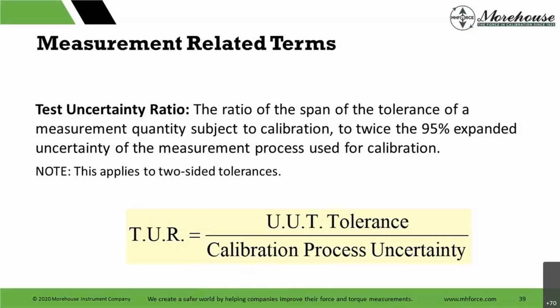The definition of test uncertainty ratio is the ratio of the span of tolerance of the measurement quantity subject to calibration to twice the 95% expanded uncertainty of the measurement process used for calibration. Now, some people might say the ANSI Z540.3 standard is kind of going away. Well, there is a committee that's going to evaluate what needs to be brought forward and what doesn't. Those that say this standard is kind of defunct, I can say the new ILAC G8:2019 also has a definition of test uncertainty ratio, which is almost the same definition.